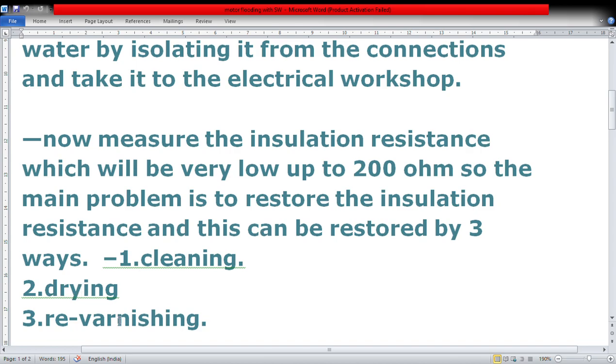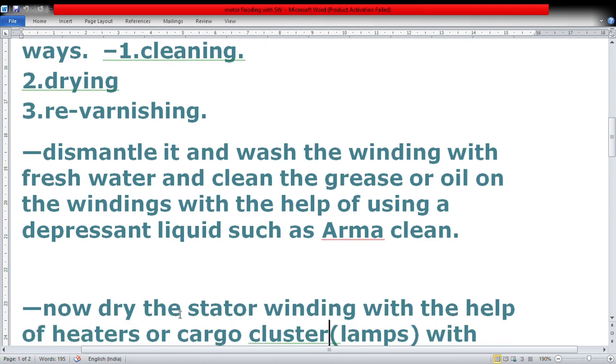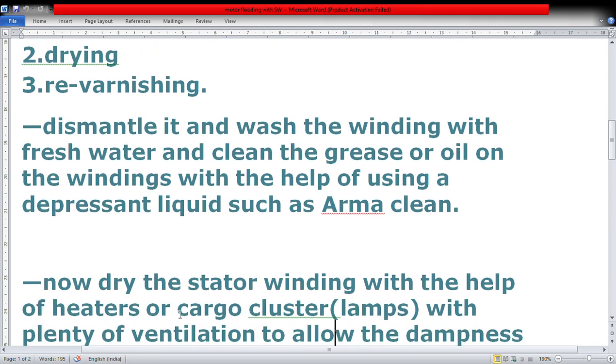Dismantle the motor and wash the windings with fresh water. Clean the grease or oil on the windings with the help of a dispersant liquid such as Arma Clean. This is very important because there may be grease, oil, or salt deposits since it was submerged in seawater.